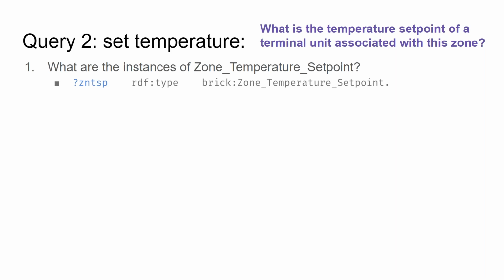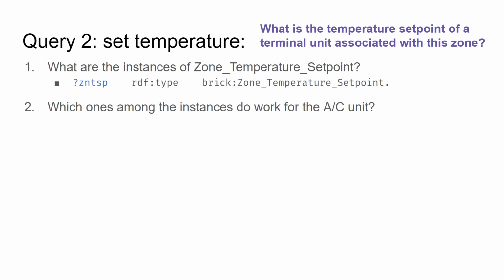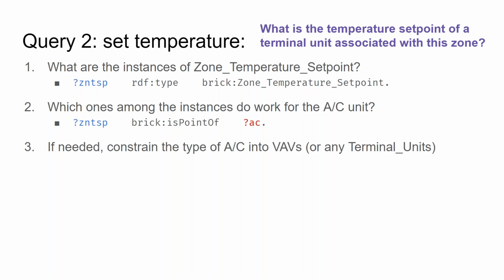This process remains the same: we look for instances of zone temperature set point, and we want these set points to be associated with an actual AC unit. We could specify the type of AC unit further as a VAV, but since Brick provides a great hierarchy of abstraction, an application can choose the right level, such as terminal units, which is a superclass of VAV. Since different buildings may use VAV, fan coil units, or space heaters, if we want our app to be general enough to cover any of those, we can specify terminal units instead of VAV.